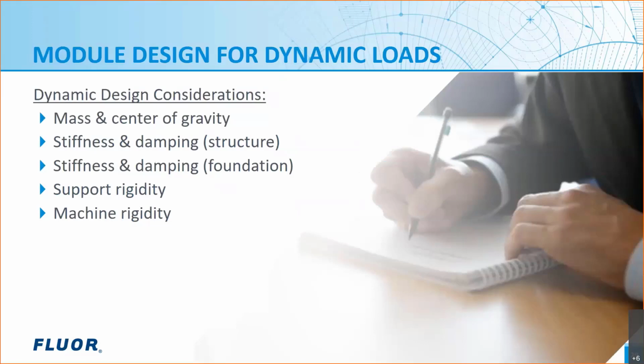Rigidity of machine support is applicable to any situation, but becomes significant when supporting on steel framing. Support rigidity is needed to maintain shaft alignment and to allow cancellation of internal machine forces. As a cautionary note, the rigidity of the machine itself is commonly oversimplified and can contrast with the supplier's rotor dynamic analysis. I've seen many structural analysis models that assume the machine is completely rigid. This can be an invalid assumption, especially for larger machines.